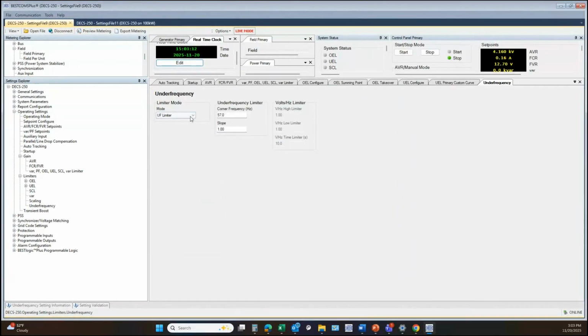Going back to limiters, the last one we're going to worry about is the under frequency limiter. You have a choice of either under frequency limiter or volts per hertz limiter. If you leave it at under frequency limiter, basically, if you're defining a knee point, if your generator frequency is above that knee point, it doesn't affect the DECS operation at all. But once your generator frequency starts to drop, then the DECS will start reducing voltage to help your engine recover. Because the engine is actually what controls your generator frequency, not the DECS. The DECS controls your voltage, it controls excitation, it controls the amount of reactive power being produced by the machine, but it does not control your frequency.